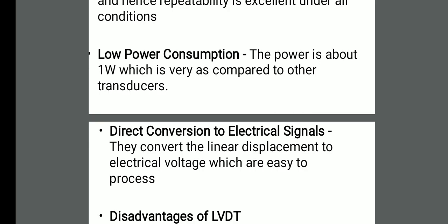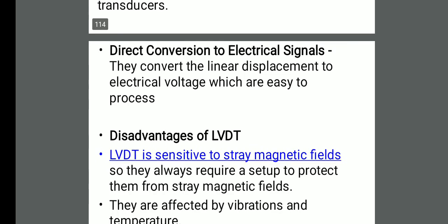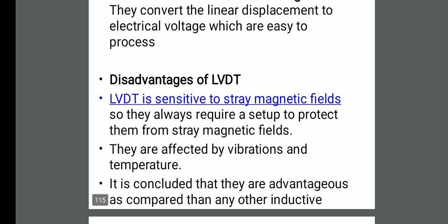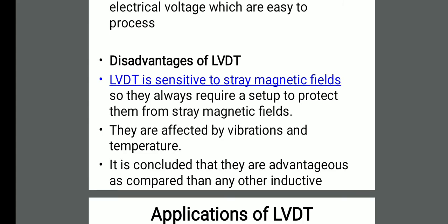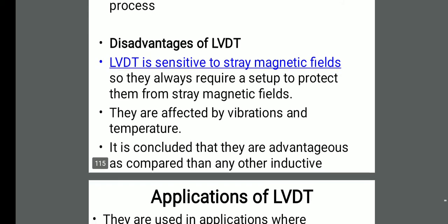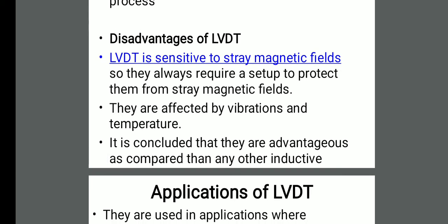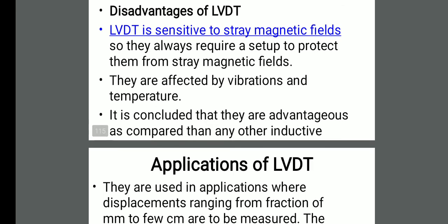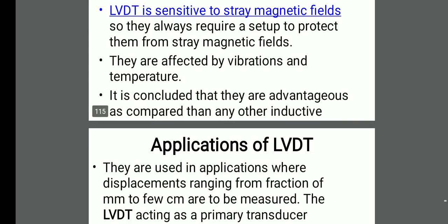The disadvantages of LVDT are that it is sensitive to magnetic fields. If an external magnetic field or electrostatic force acts on the LVDT, it may interact with the flux and cause wrong readings. To prevent this, the LVDT is kept in a steel casing. They are always required to be set up with protection from stray magnetic fields, and they are also affected by vibrations and temperature.